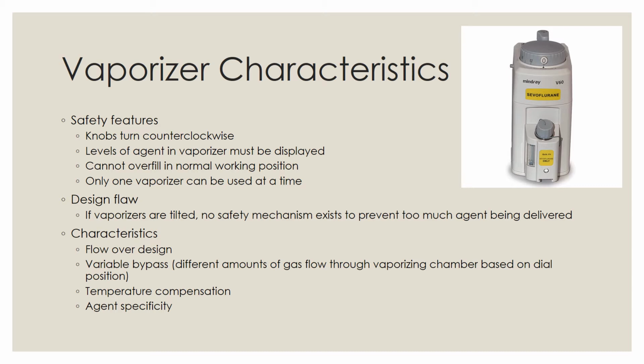You cannot do it. The one design flaw of modern vaporizers is if you knock a vaporizer over, there's really no safety mechanism to prevent the anesthetic agent from sloshing around the inside and getting into all of the various chambers. So if this happens, there's really no safety mechanism to prevent too much agent being delivered. You have to put the vaporizer off to the side and let it resettle and find another vaporizer to use.